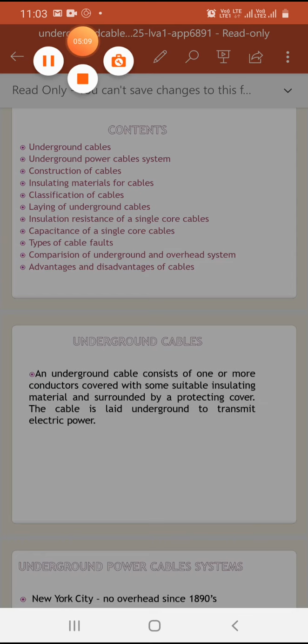Our first requirement is that the conductor used in cables should be tinned stranded copper or aluminum of high conductivity, and stranding is done so that the conductor becomes flexible and can carry more current. The next requirement is that the conductor size should be such that the cable carries the desired load current without overheating, and the voltage drop is within permissible limits also.